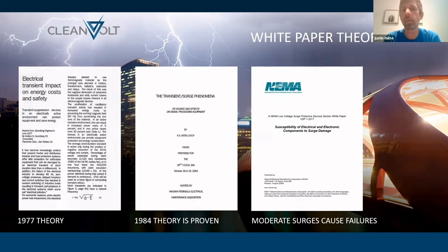You can hook a meter up to a service for a year and you might get lucky, or depending on how you look at it, unlucky enough to record one or two peak voltage rise situations within that system. But there are energy surges happening constantly, and they're found on the current waveform. So it's important to keep these 3 white papers in mind.